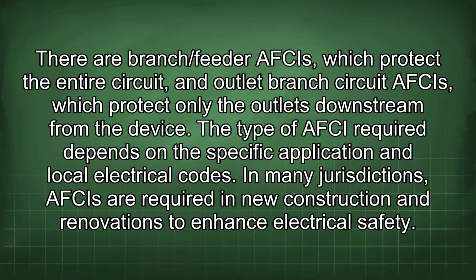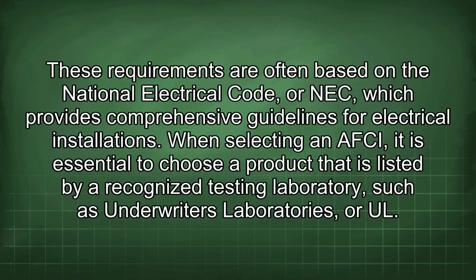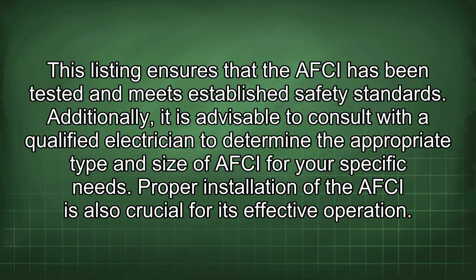Furthermore, it's important to understand the different types of AFCIs available. There are branch/feeder AFCIs, which protect the entire circuit, and outlet branch circuit AFCIs, which protect only the outlets downstream from the device. The type of AFCI required depends on the specific application and local electrical codes. In many jurisdictions, AFCIs are required in new construction and renovations to enhance electrical safety. These requirements are often based on the National Electrical Code, or NEC, which provides comprehensive guidelines for electrical installations. When selecting an AFCI, it is essential to choose a product that is listed by a recognized testing laboratory, such as Underwriters Laboratories, or UL. This listing ensures that the AFCI has been tested and meets established safety standards.